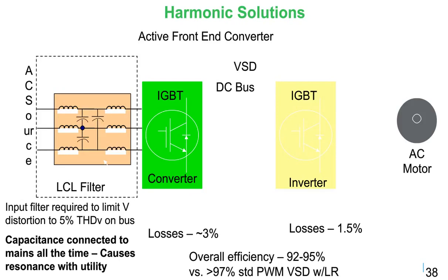Okay, so I don't want to spend too much time on this slide, but a few of the key takeaways of the active front-end converter, as I pointed out in some of the early discussions, is note the input filter is required to attain the THDV limits. It is a broadband filter, and heat losses are up to 3 to 4%, and the physical size is equal to the VFD size it's applied to. And the overall active front-end VFD efficiency typically drops to less than 95%, which is still strong, but you will potentially, depending on your utility, get charged for under 95%, whatever is stated in your local market, versus a standard 6-pulse VFD with a line reactor, which is typically over 98%.